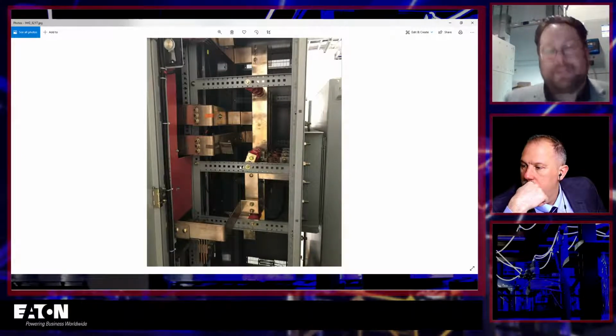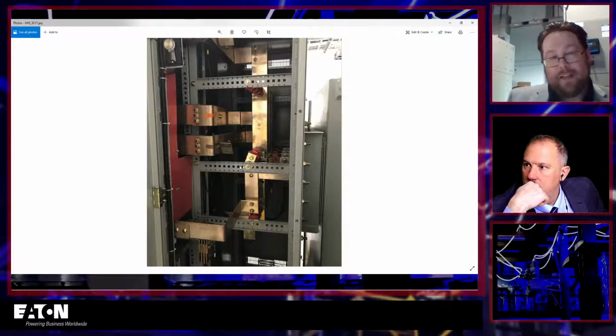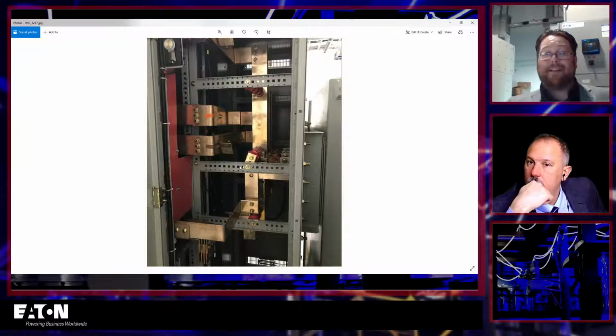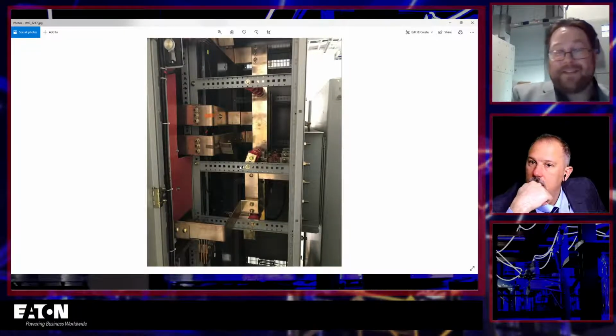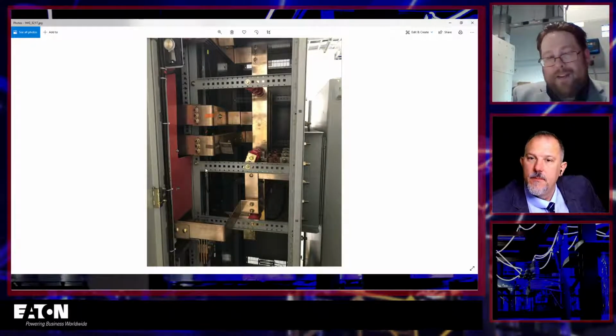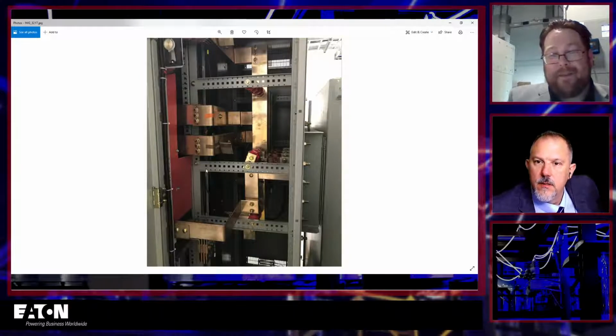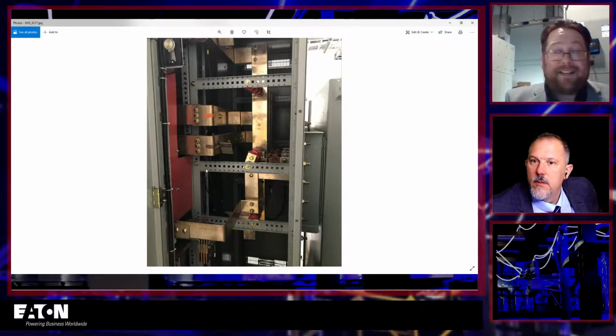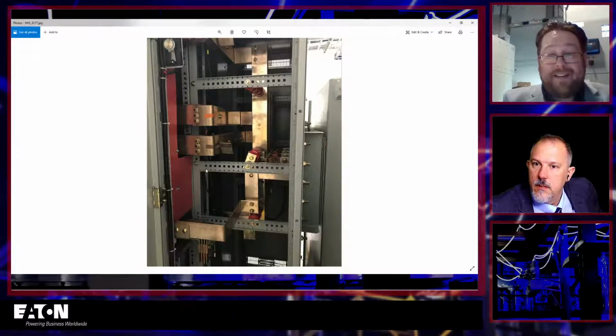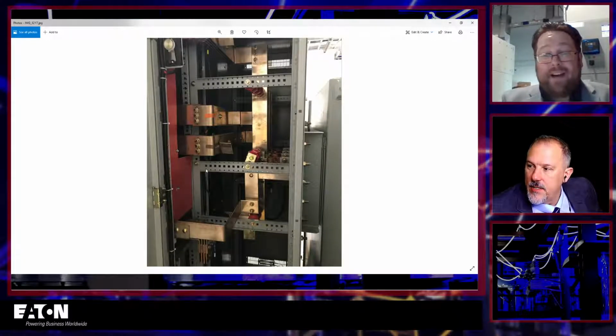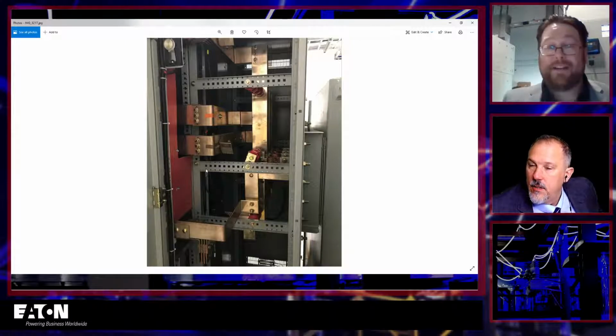It's almost impossible to take a picture of without getting in the switchgear. To the left, behind the barrier, is actually where the neutral to ground bond is inside the switchgear. As well as, you're going to love this, if you looked on the side of the transformer, there's the grounding strap on there too. So in this one section of switchgear, we actually grounded it twice, the neutral to ground bond. Wow, interesting. So weird things happen.